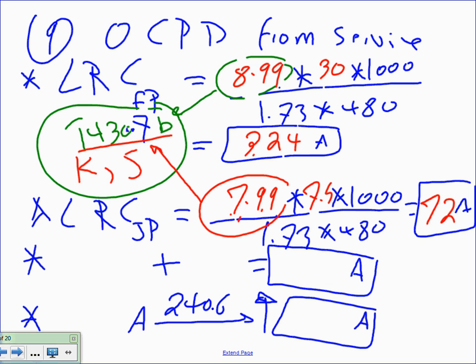Cool. So first, step 1, find the locked rotor current for the fire pump. Step 2, find the locked rotor current for the jockey pump. Step 3, add the 2 together. So we're going to have 324 plus 72. And Chris, if you passed the 5th grade, you should be able to come up with 396 amps.